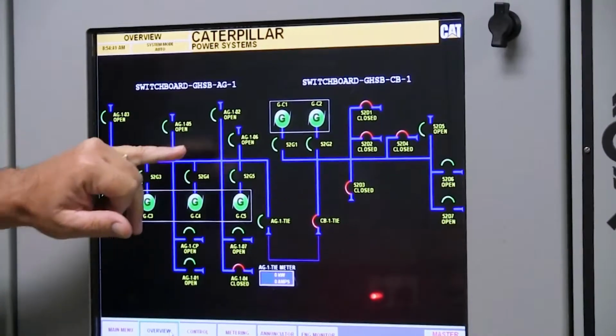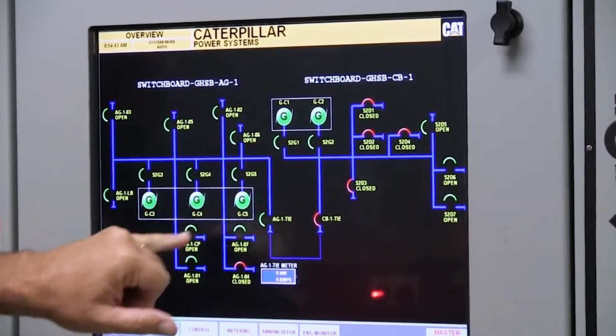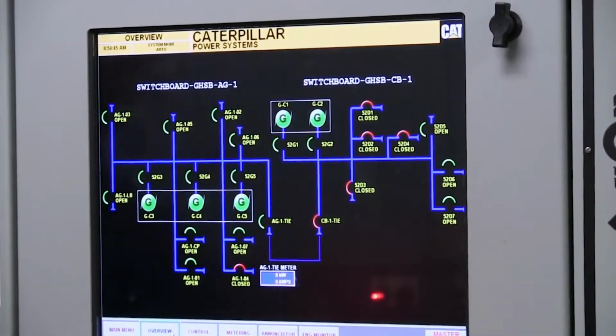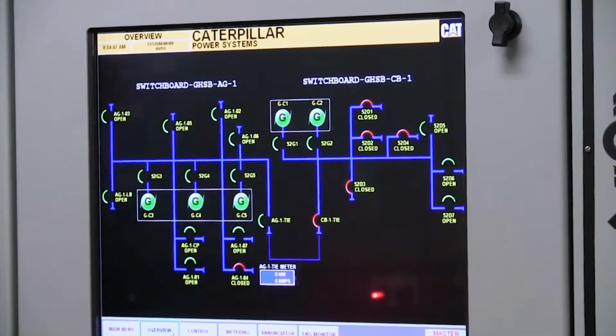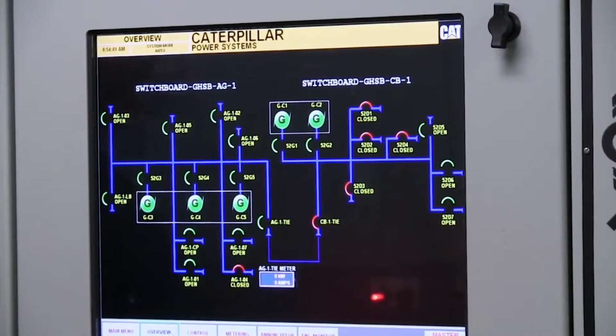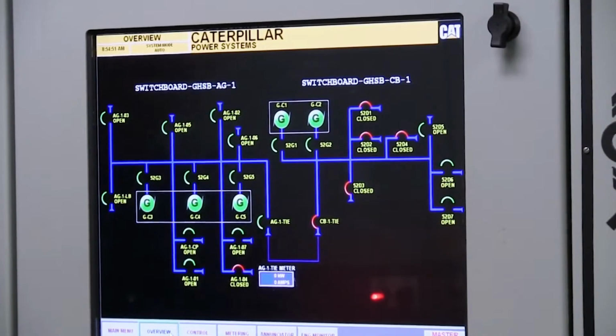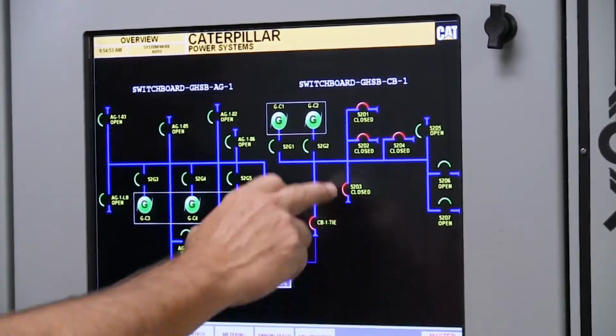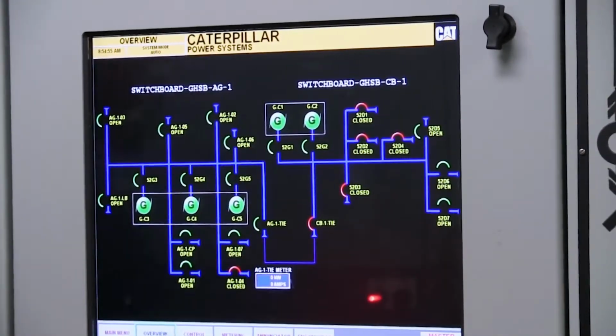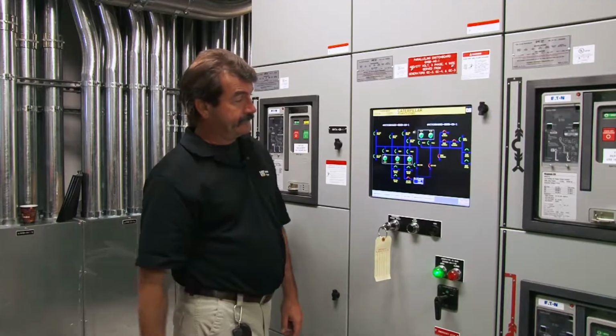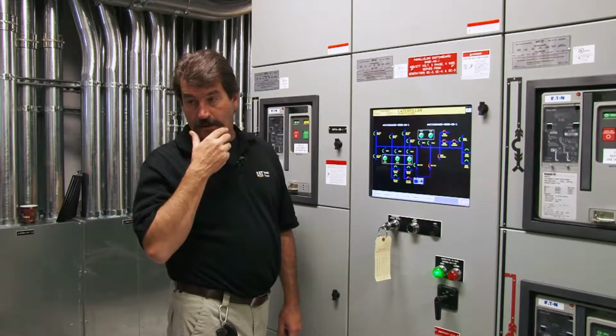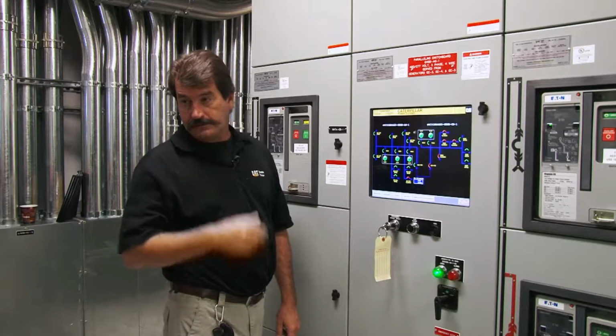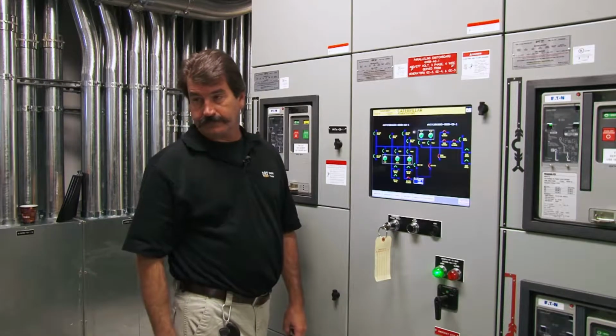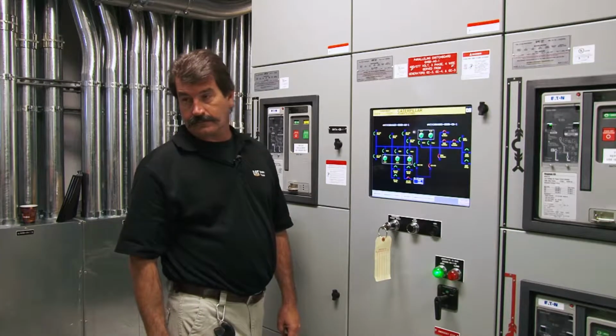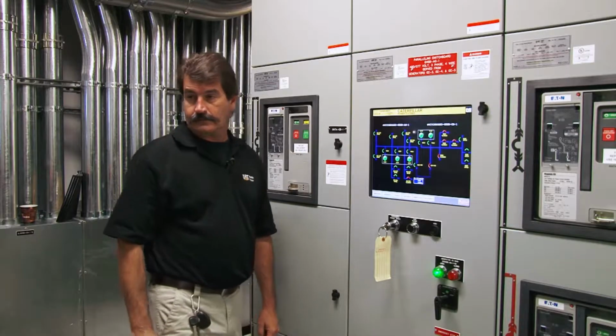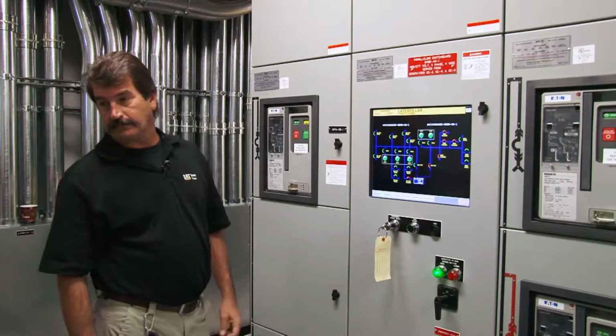Right now, I see that these are open right here. So if these are open, you must have a conditional load shed on here, because you've only got one normally closed here. All the rest of them you have closed down there. The closed ones are all the critical circuits. That goes to all our ATSs. The open ones are the not critical circuits, and they're timed in.